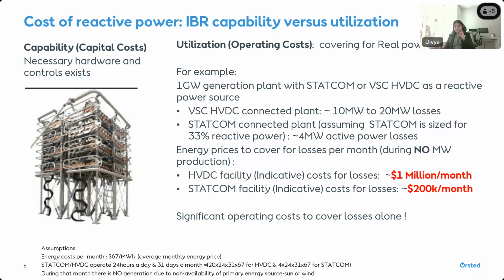So it's always found more cost effective to have an onshore transmission device like a STATCOM, and if it's a DC connected offshore wind plant, we'd use the onshore converter station to operate like a STATCOM and provide the necessary voltage support. This is a clean case where you don't have to look at losses from cables and other equipment, just onshore equipment. In most cases, the onshore substation is located very close to the transmission facility or POI where it's connecting, so small AC line losses can be neglected and we're just looking at the transmission connected equipment.